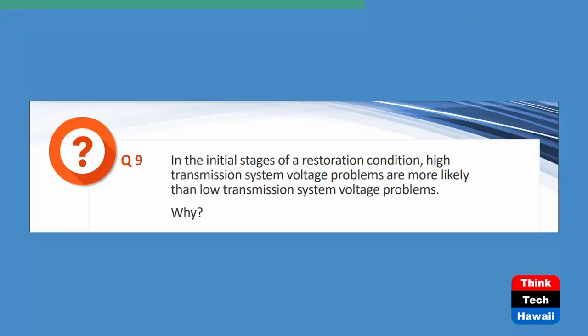The next question is, in the initial stages of a restoration condition, high transmission voltage problems are more likely than low transmission voltage problems. Okay, why? Well, let's talk about what happens in a blackout restoration system. So in a blackout, basically all of your generation is shut down. You have likely been separated from the interconnection, you're on your own, and all of your system is connected through closed breakers, but you are de-energized.